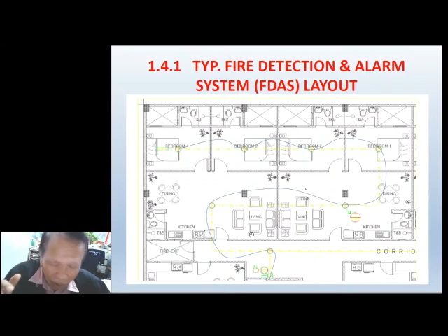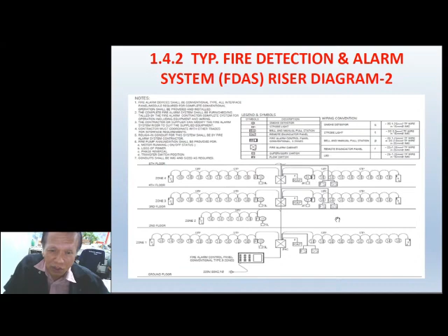So the riser diagram for an FDAS looks like this. Most of us electrical practitioners are already familiar with this. I also added some calculations for the feeder of the home run circuit for the fire alarm and control panel, because usually the load is quite small - about 3.2 amps for one I checked. You have to check the AC ampere input to the fire alarm control panel to determine the home run circuit. I'm pretty sure the load of the FACP, the fire alarm control panel logic device, is small, so the circuit is only 2.0 mm square.